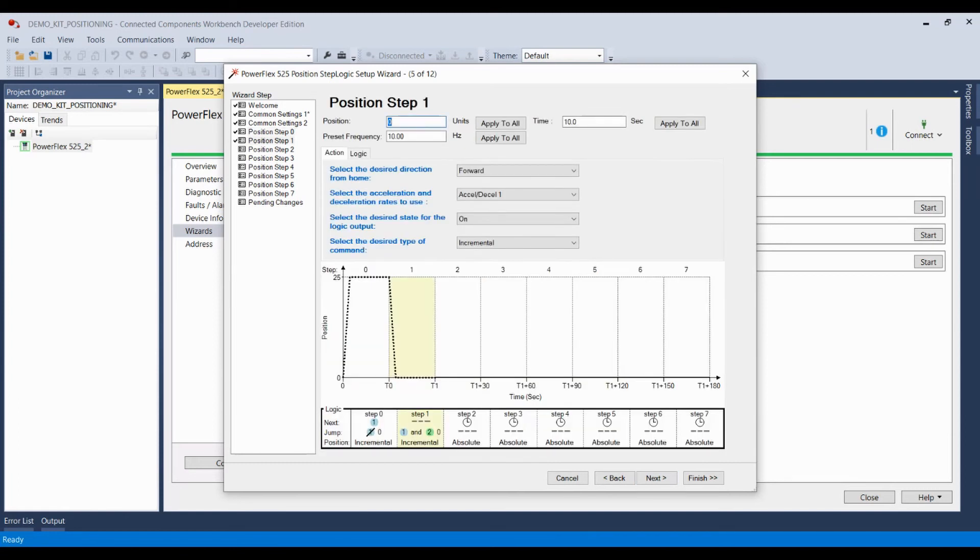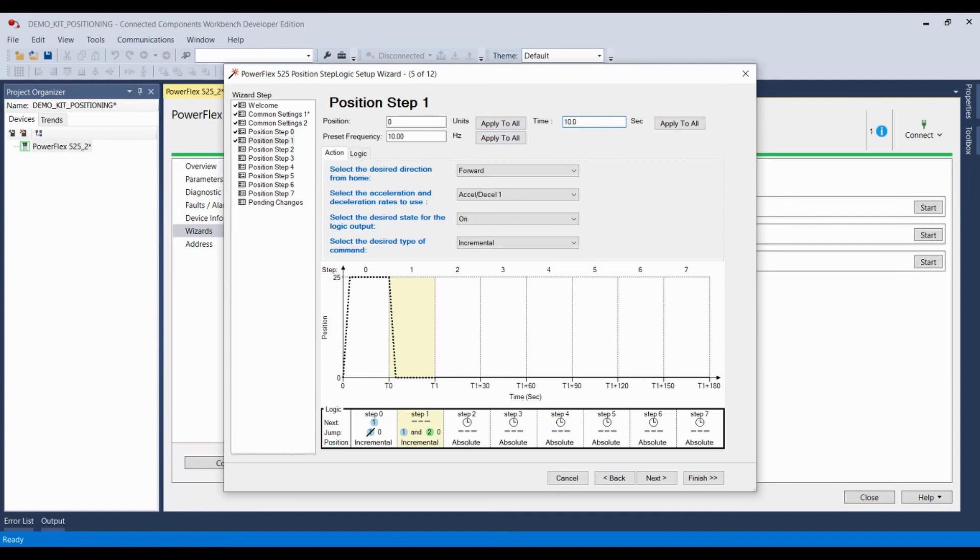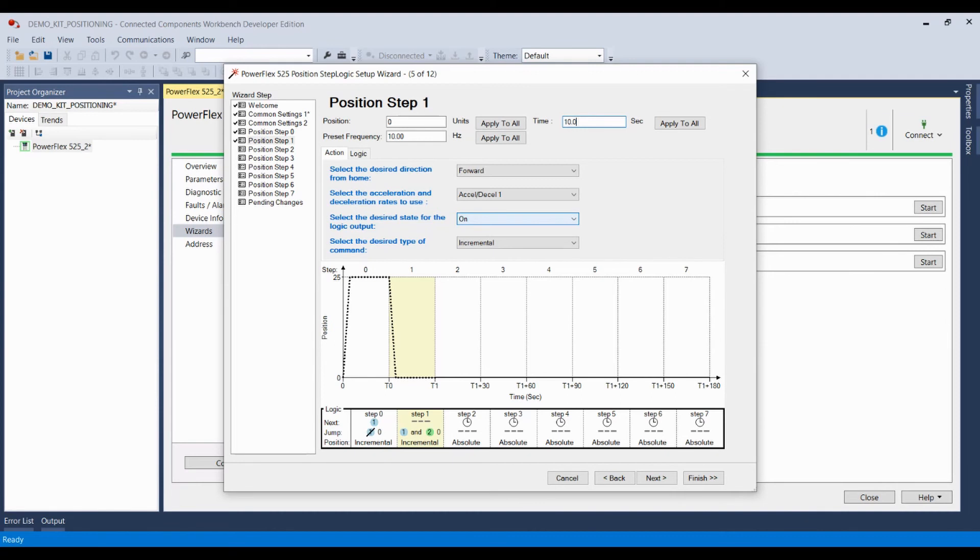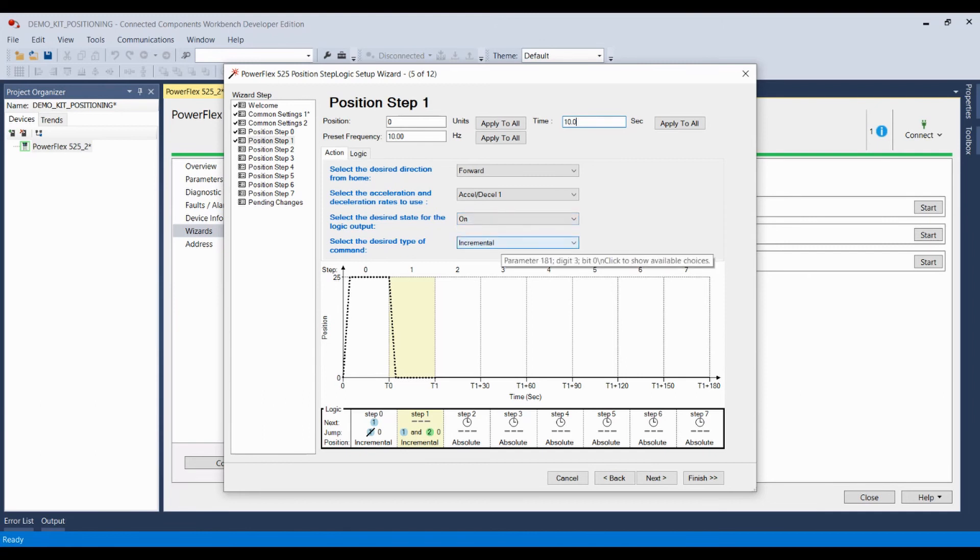Now moving on to the next step, step one. For step one, my system is not going to move. So my units of motion are zero. My frequency is still 10 hertz and my time is 10 seconds. As you can see, you can simply say apply to all and every one of your steps will simply take on these values. Now, in this case, I've had this set to forward and accel and decel one because I'm not moving. This actually doesn't matter. But notice here, my state of my logic output is on. What this means is once I reach step one and you reach this step, once that position sensor for the receptacle is activated, this drive is going to engage relay one, which will send a signal out to the controller for the dispenser, letting it know that a receptacle is in position. So this is how my system, my drive is going to let the dispenser know that it's pushed a receptacle into place. Now, here and again, my move is incremental because I have no reference to home in this case. I'm just moving forward every time a receptacle has been filled.